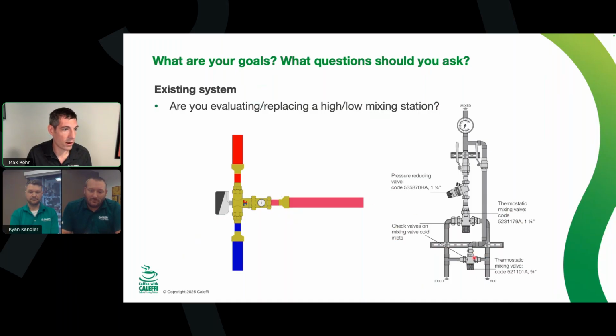If you wanted a high-low thermostatic mixing station, we used to ship it with the Unistrut and everything in a rack assembly, ready to plug in. It included a 3/4 inch mixing valve, a 1.25 inch mixing valve, and a 1.25 inch pressure reducing valve. What we found is this is a lot of brass, versus a digital mixing valve where you might only need a 3/4 or 1 inch valve, which was a lot more cost competitive from a material standpoint. Even with the controller, the digital mixing valve ended up being close to price parity in our catalog.